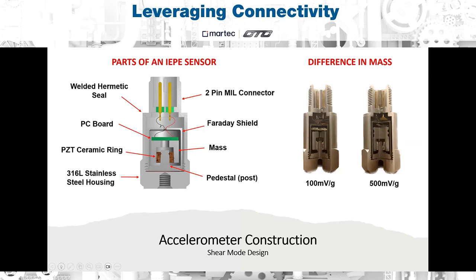Another thing I'd like to point out is that all CTC sensors are hermetically sealed. During the manufacturing process, the sensor is purged with helium and welded shut. The sensor then goes into a vacuum where we try to pull out any of that helium. This ensures a complete hermetic seal, and there are no leaks or cracks in the weld seams that could lead to ingress issues. The final thing I'd like to point out is the difference in mass size that you see there on the right of a 100 millivolt per G sensor compared to a 500 millivolt per G sensor. As you can see, the mass on the 500 millivolt per G sensor is much larger. This diagram was included to show that we offer a true low frequency accelerometer. Again, other suppliers market their sensors as being low frequency. However, all they're doing is amplifying the low end signal, which will not provide clear and accurate data, specifically for low speeds.